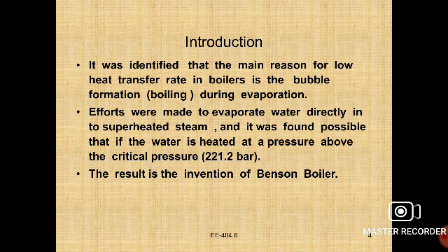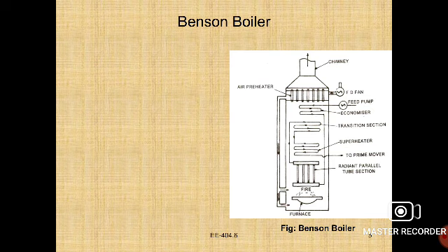It can operate at the critical pressure, that is 221 bar, where the steam and the water have the same density, and therefore the danger of bubble formation can be easily eliminated. Water transforms into steam without boiling, that is, latent heat is zero. The Benson boiler was first operated in 1927 in West Germany. So this is the introduction for the boiler.